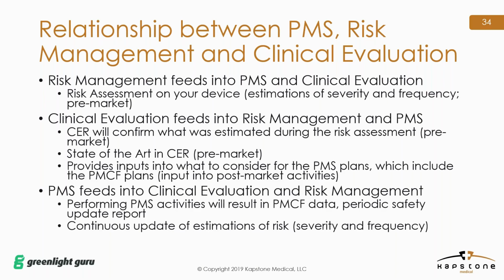But a little bit more specifically, risk management feeds into your PMS and clinical evaluation. As a pre-market activity, you're doing a risk assessment on your device. You're estimating severities and frequency of certain potential hazardous situations and subsequent harm. So your risk management feeds immediately into your post-market surveillance and clinical evaluation. Then you have your clinical evaluation report, which is confirming what was estimated during your risk assessment. So again, another pre-market activity.